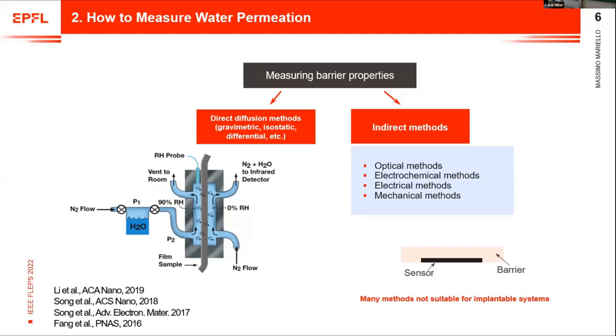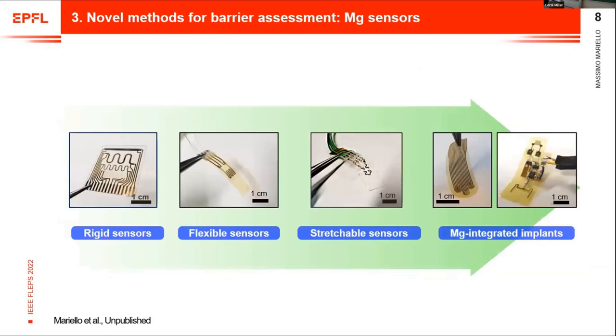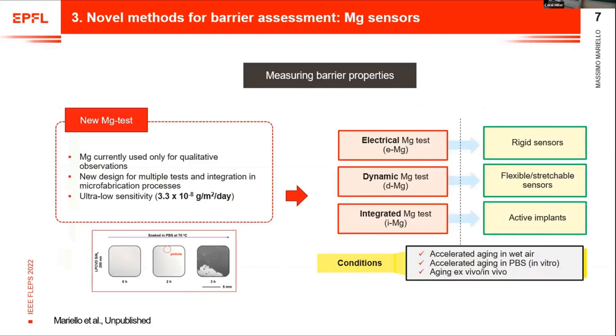Many of these methods are not suitable for implantable systems, so we developed a new method called the magnesium test. This method is based on magnesium sensors and real-time monitoring of the electrical resistance of magnesium micropatterns. This provides the lowest sensitivity among all methods mentioned: 3.3 × 10 to the minus 8 grams per meter square per day — a record value.